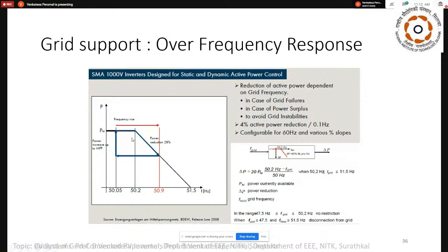But if the load demand is not there and the generation is more, then the frequency keeps on increasing. So most of these PV inverters work on frequency control. If the frequency crosses 50.2, the percentage reduction in power will start. Okay, the slope at which the power is going to reduce is there to support the system stability.